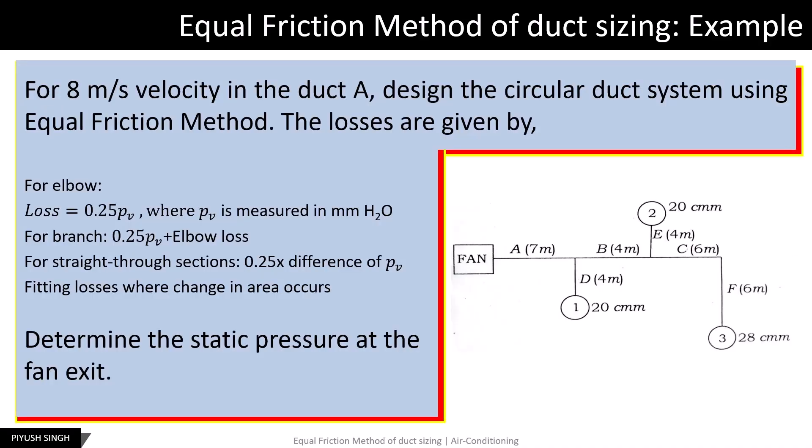Now, suppose that in addition to the frictional losses, the dynamic losses are also given — for example, elbow loss, branch loss, and straight-through section losses, also known as fitting losses — and we are asked to determine the static pressure at the fan exit. In this case, steps 1 to 5 remain the same. After compiling the table, we proceed to determine the dynamic losses and static pressure at the fan exit.